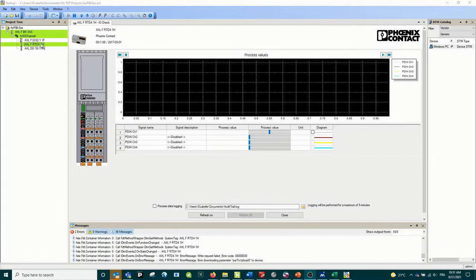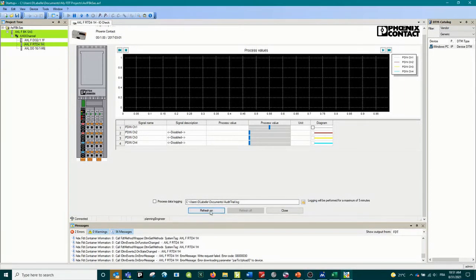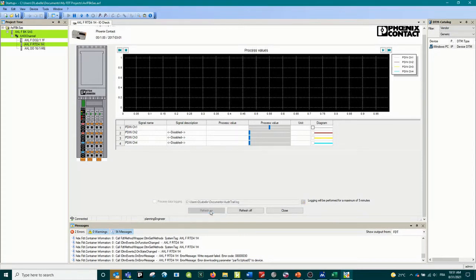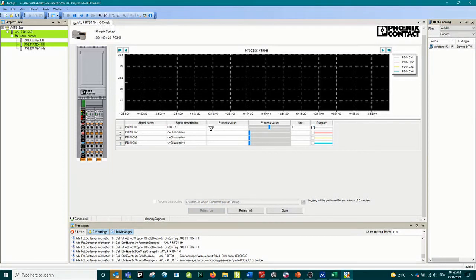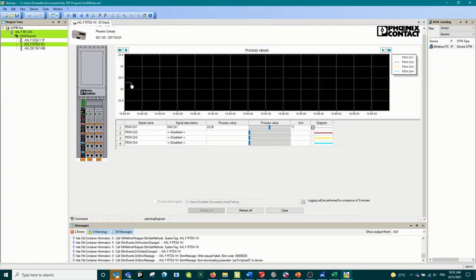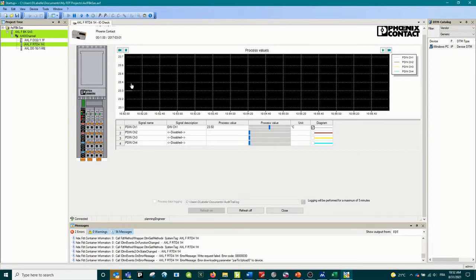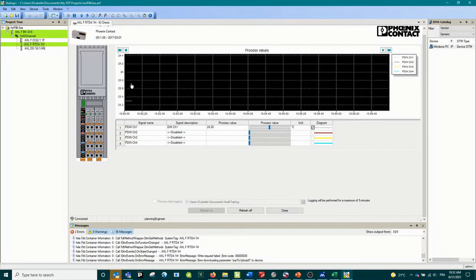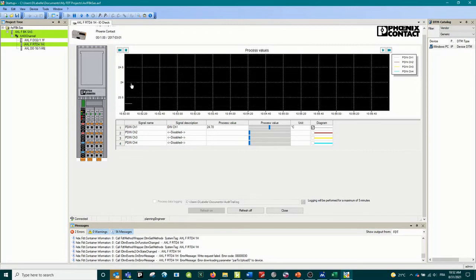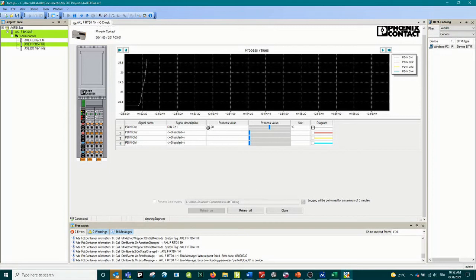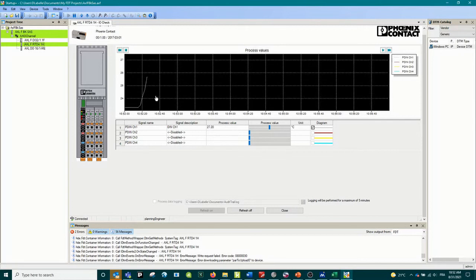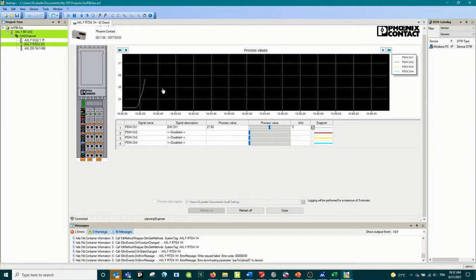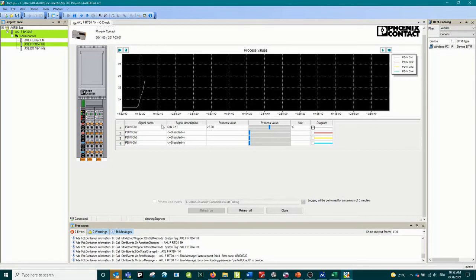Inside the RTD card I can press over here on refresh, pick the one I would like to see, and right now I have the temperature which is 23.30. As you can see over here on the graphic, I'm just going to play a little bit with the sensor so you will see the temperature going up. Under process value over here you are seeing that the temperature is changing and now we have a graphic view also of the temperature.